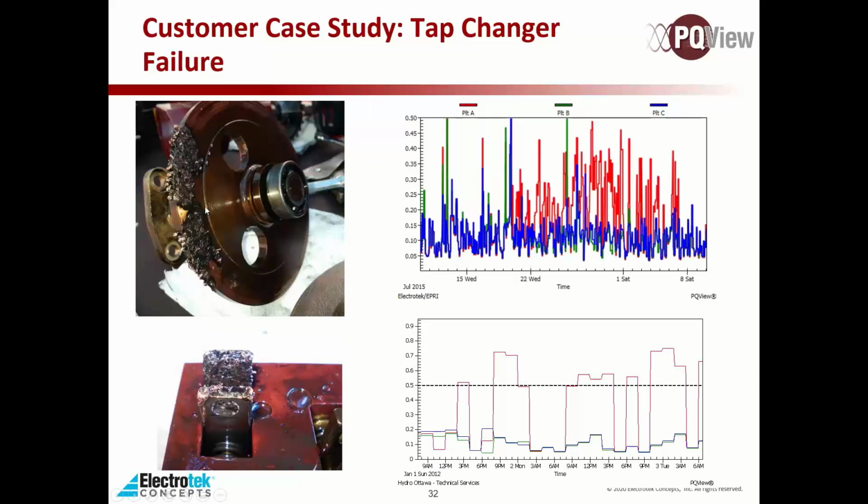If you're interested, attend one of our users group meetings. It's worth noting that this would have taken the transformer with it likely. And so you're talking about quite a lot of money saved by finding a tap changer.